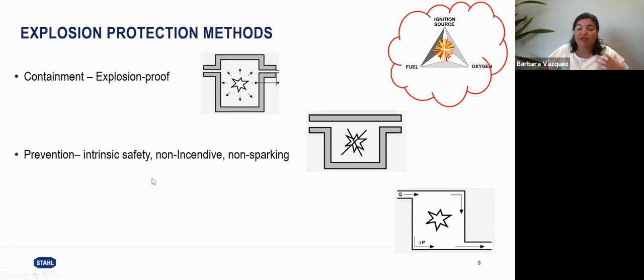Another protection method, or another principle for protection, will be prevention. Prevention says the spark, the heat, that high energy will not happen in the hazardous area. So you will not have enough energy to react with that explosive atmosphere. Examples of that will be intrinsic safety, non-incendive, non-arcing, increased safety, that type of protection methods. So it does not rely on the enclosure. It relies on all the components.